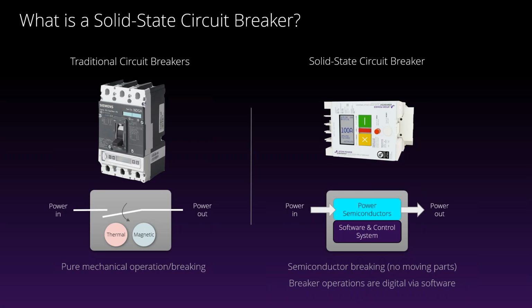So that's more for overload events. If you're just slightly above the rating of the circuit breaker, it's more to prevent the cable underneath the breaker from getting too hot, catching fire, and causing a thermal event. The magnetic protection is done when you have a fault and you have a huge inrush of current for that fault. There's a magnetic field around that current flow, which causes the breaker to kind of pop open. So that's how a traditional circuit breaker works.